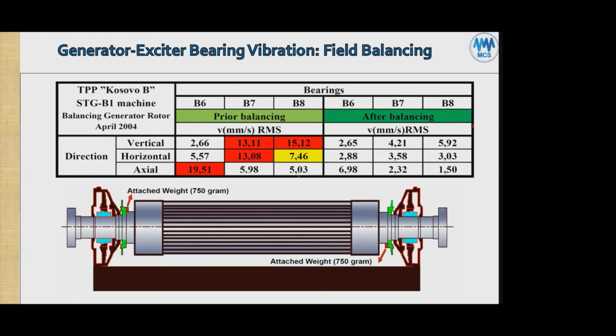Whereas when it's magnetic, the magnetic power is gone immediately as soon as you shut down the generator or motor. And so you will not see the 2x anymore, or most of it is gone. And the 1x caused by that magnetic power will go suddenly, but the remaining residual unbalance 1x will still be there. I hope we answered it properly.